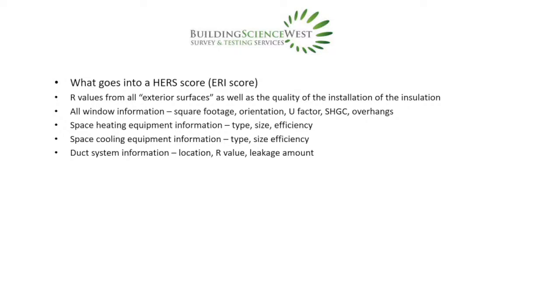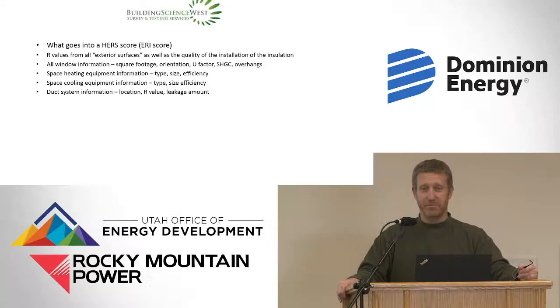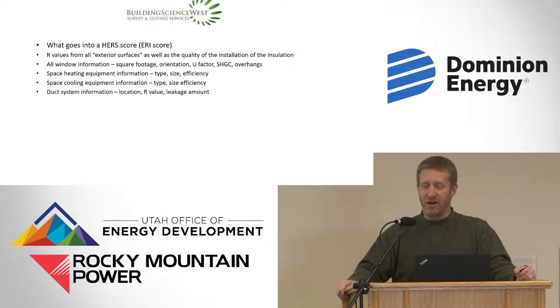Even so, code states that ductwork in unconditioned space needs to be insulated to R8. For attics, prescriptive is R49 for this climate zone. So if you're moving your conditioned air, whether heated or cooled, through an R8 duct, there's a lot of energy loss versus R49, which is what keeps the energy inside the home.